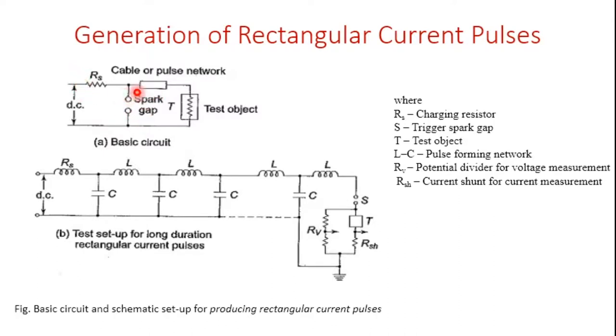When the spark gap is short-circuited, the previously charged cable or pulse network will supply the energy to the test object. Since it is very difficult to obtain a coaxial cable of sufficient capacitance and length, we use artificial transmission lines with lumped values of inductance and capacitance. Generally, 6 to 9 LC sections are sufficient to produce good rectangular waves.